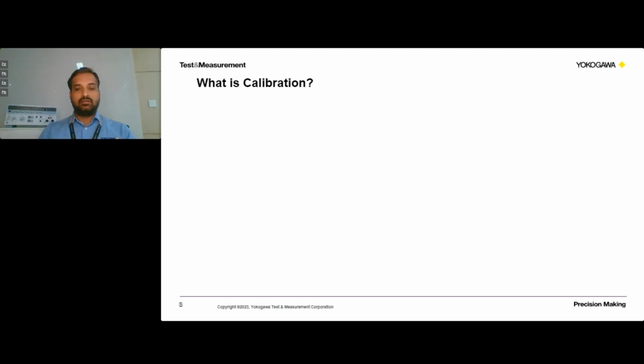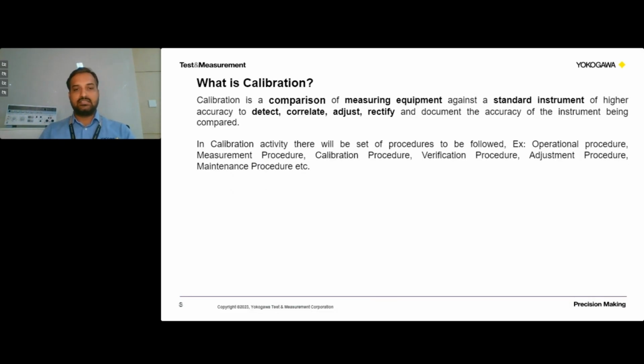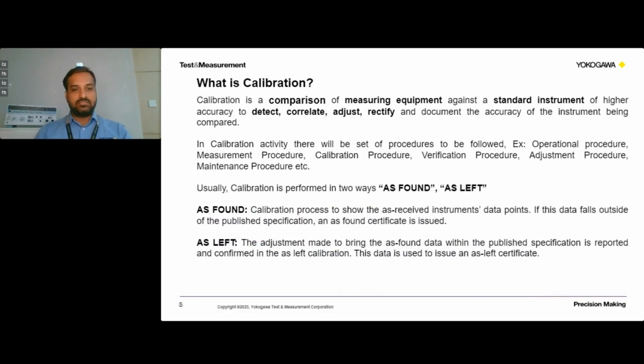In doing so, we check for errors in the DUT, and if any errors are there, we correct and adjust those errors, and then we say it is calibrated for the defined specifications. When we come across calibration, a set of procedures is followed, such as operational procedure, measurement procedure, calibration procedure, and verification procedure. When we do the calibration, we do two types: as found and as left. As found is before correction or before adjusting the error, and as left is after correction.